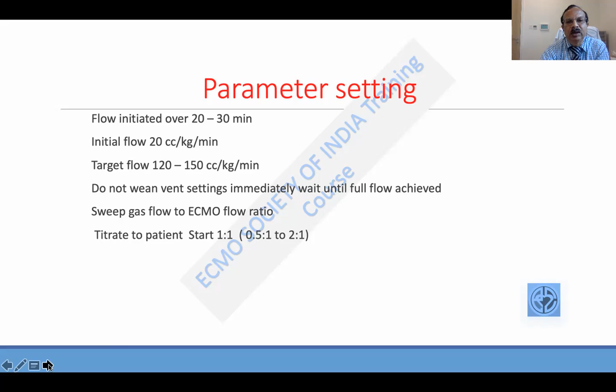The ratio of sweep gas flow to ECMO flow is adjusted according to the following formula. Titrate the patient, start with a 1:1 ratio of flow to sweep gas. Sweep gas is the oxygen supply going through the circuit, as you know by now. The ratio of gas flow to the ECMO blood flow is maintained at 0.5 to 1 to 2 to 1. Don't exceed that. Otherwise, it can cause air embolism.